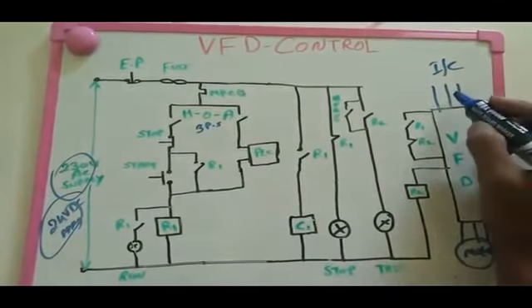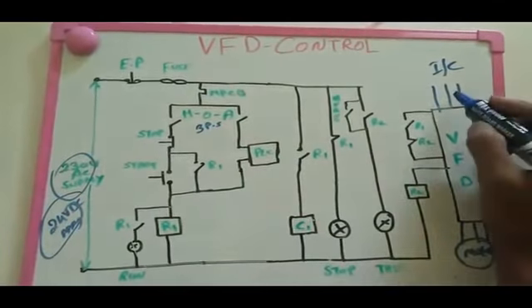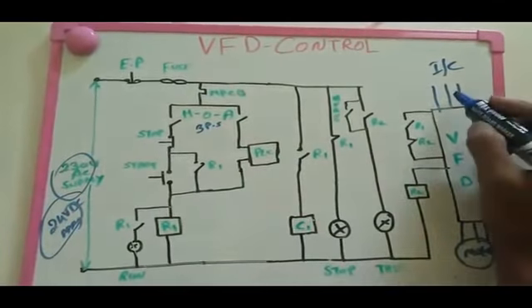The R1 is going to switch on, and this triggers the main contactor C1. So when R1 closes, C1 also closes. The R1 closing sends the start signal to the VFD. When R1 is closed, C1 is closed - that means we can switch on. The VFD is switched on through R1, so the motor gets supply. This is the manual operation.